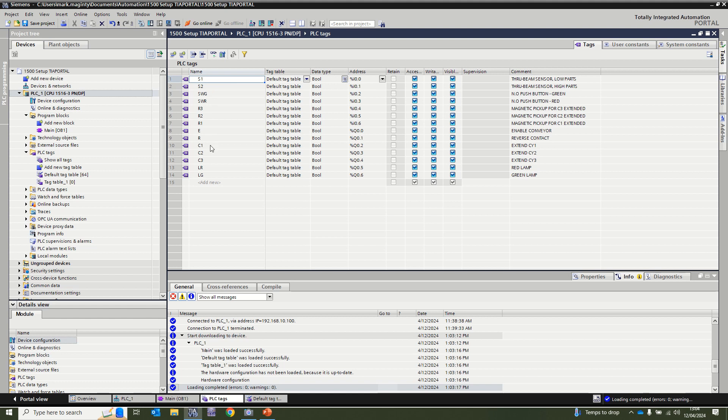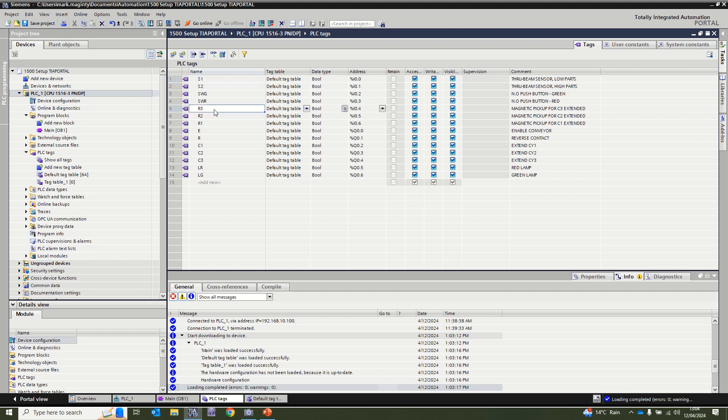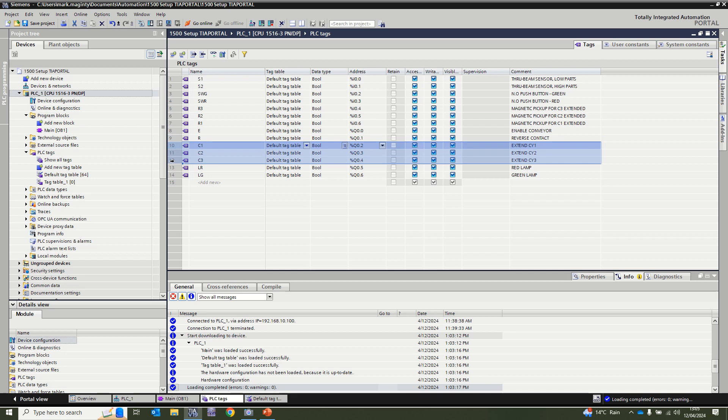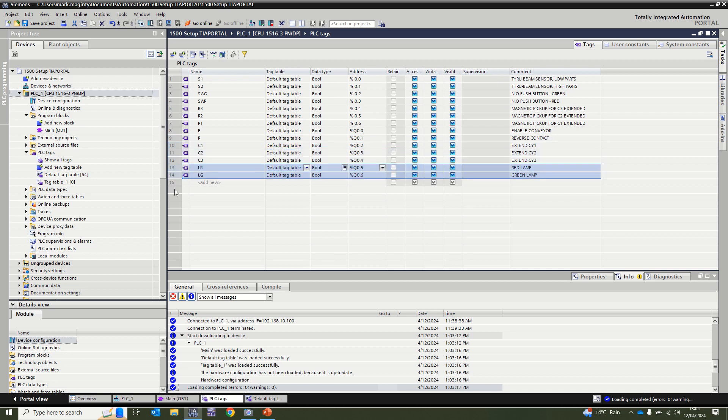We're utilizing our tag table for the conveyor rig. We have S1 and S2 which are high and low beam sensors, SWG and SWR which are switch green and switch red push buttons, and three sensors R3, R2, and R1 which are extended sensors for the three cylinders. Output-wise we get E which is enable to turn on the conveyor, R which is a reversing contact, so to go forward you need E on, to go reverse you need E and R on together. Then you get your three cylinder outputs C1, C2, and C3, and then two lamps, red lamp and green lamp.